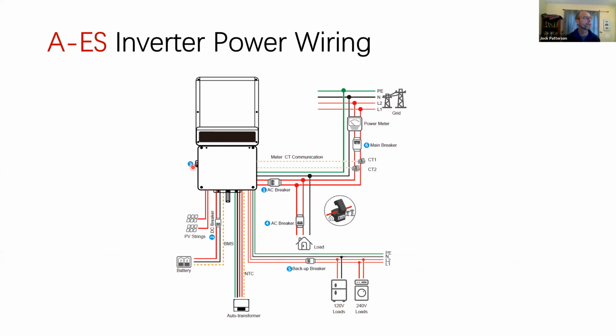Right. So it's pretty straightforward. When we talked about the PV one, you've got PV strings coming in, up to 4 strings here. And I'm assuming you can see my laser. And then the next over would be on the DC side. The left side is a battery input. The same lines are used for input and output, charge and discharge. But there's also a communications line, the one that's marked as BMS. We have to talk to the battery. This is not a dumb battery.